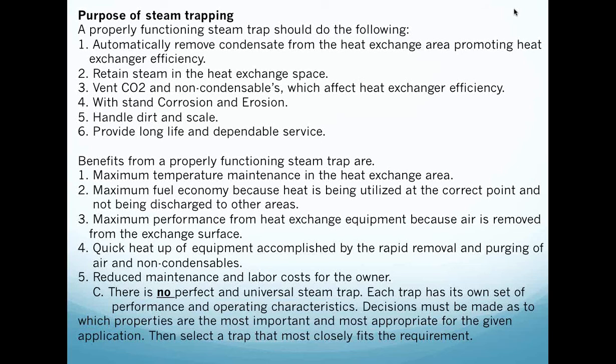I recently had someone come to me with a dislike of a particular trap technology and said, I don't like that trap because it does not stand up in my system. And I said, can you send me a picture of how your trap is located? And unfortunately, gang, what they had done is they had put that steam trap in a position where it was never going to be successful, meaning it was on the bottom of a mud leg that was never cleaned, and the steam trap happened to be at the lowest elevation, and all of the garbage that was in that system ended up in that poor trap.